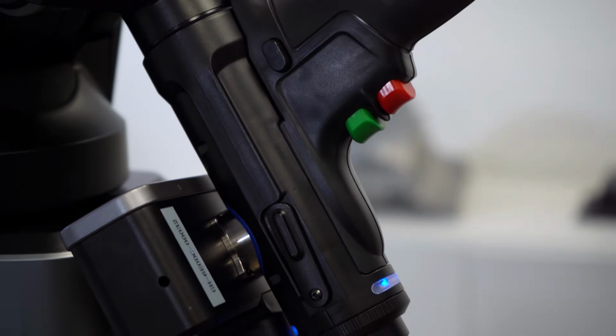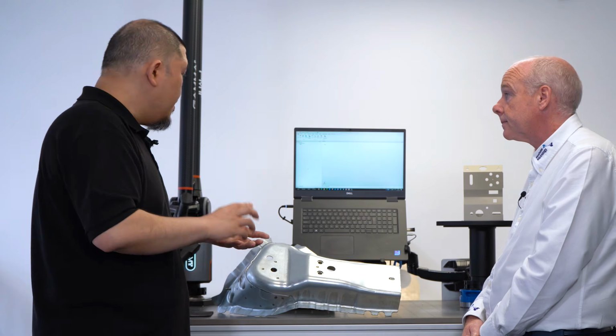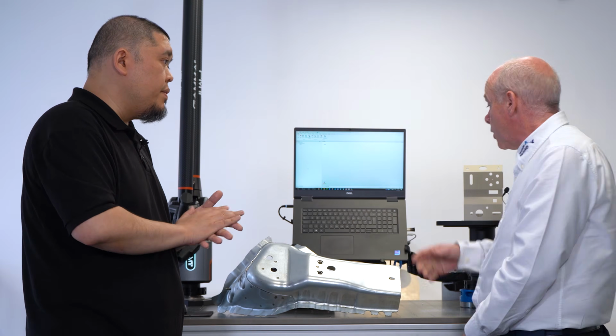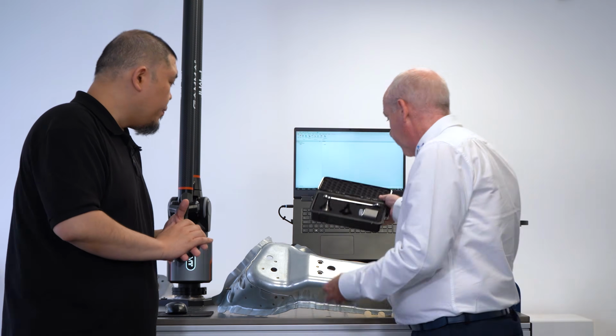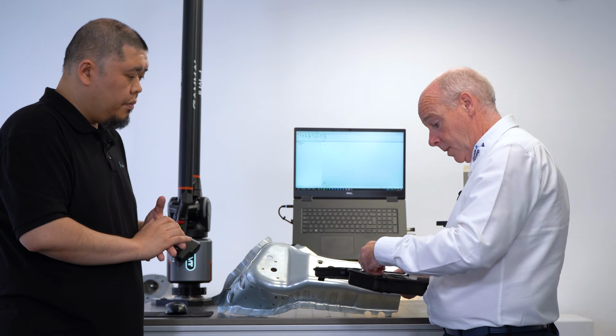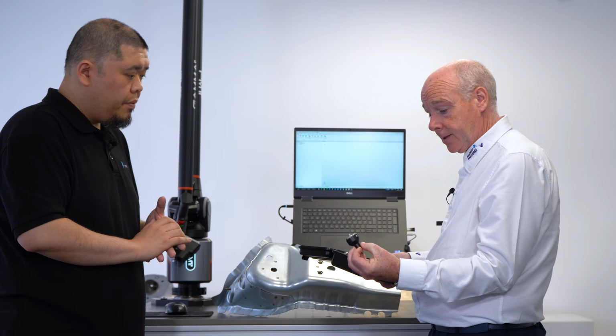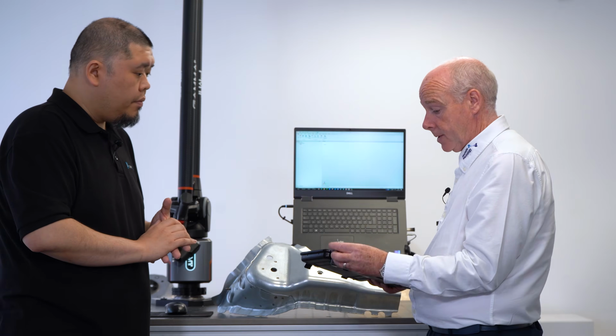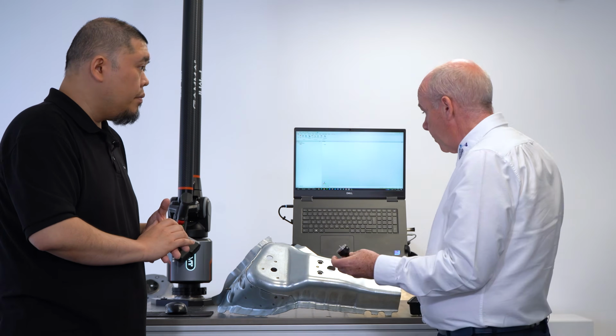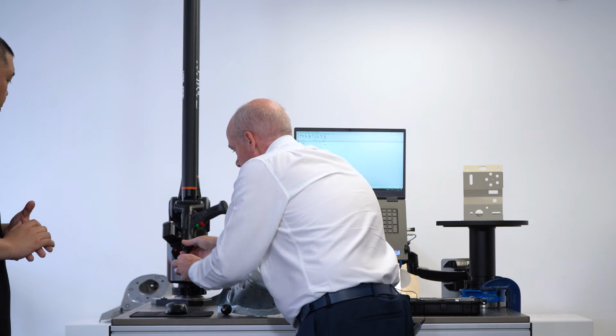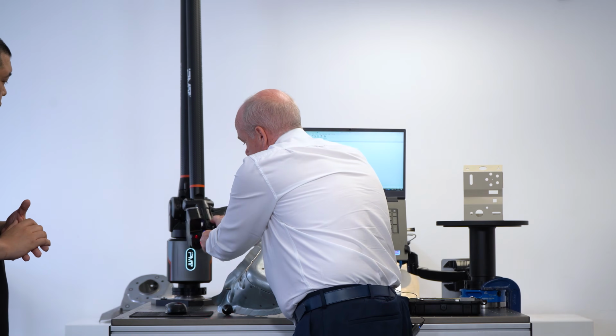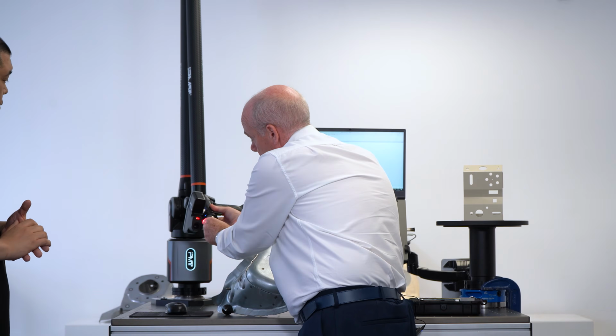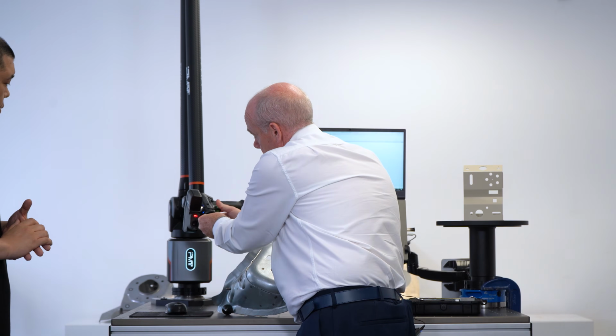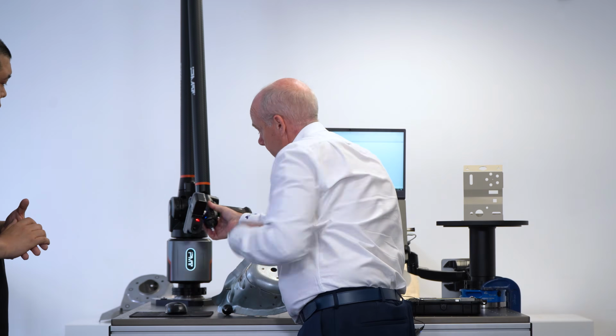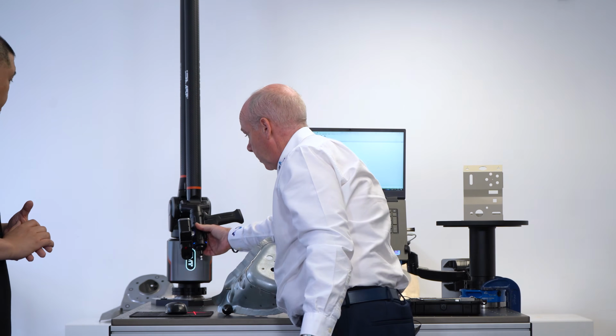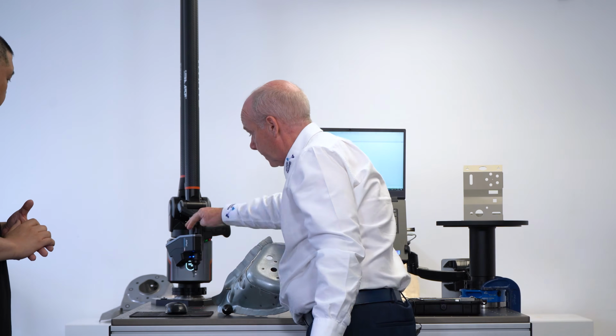So Paul, besides the probes and the calibration items, what else can you purchase with the PMT? It comes as standard with your standard 3mm kinematic probe. The idea of that, obviously, is that it's hot swappable. Because it's got its memory, you can just remove it from the arm. The biggest advantage is you can just unclip it. When you've got your new one, you've got your arrow to the top, and it remembers its position. So you can do that with 3 or 6mm and also the laser scanner.